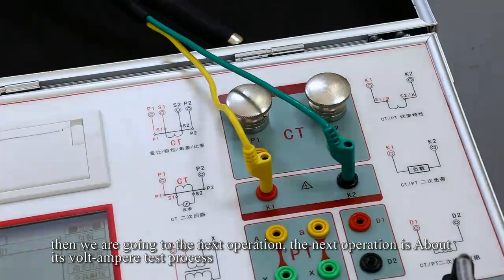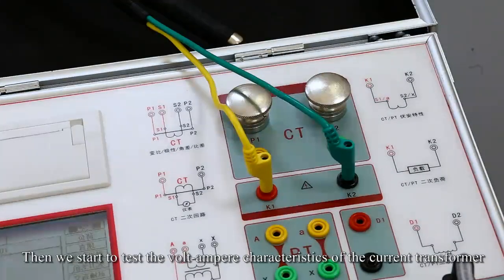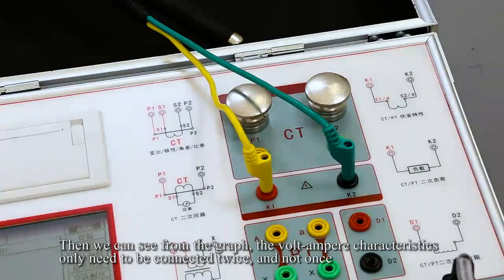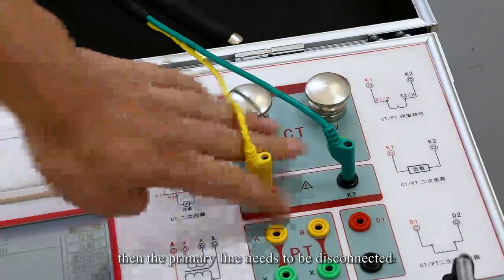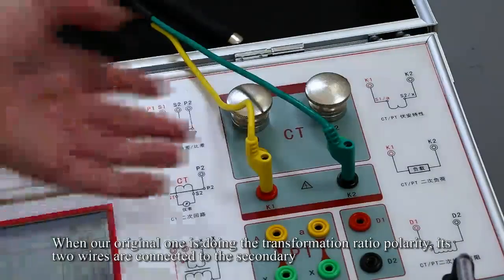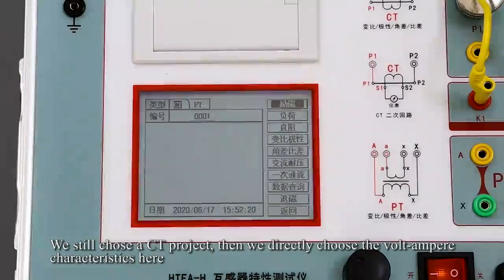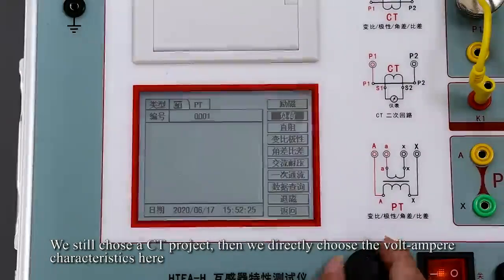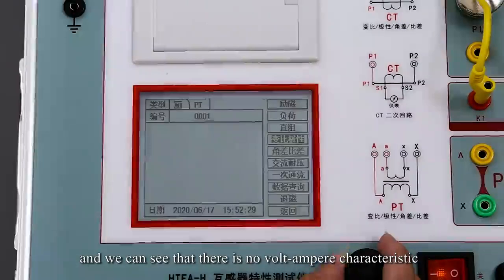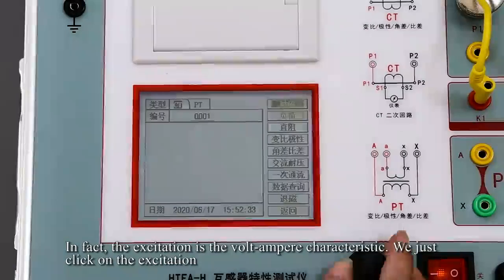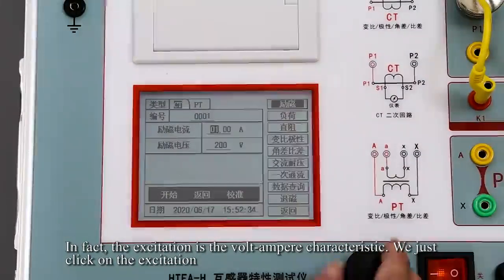The next operation is the volt-amp test process, where we test the volt-amp characteristics of the current transformer. From the graph we can see that the volt-amp characteristic test only needs to be connected twice, and the primary line needs to be disconnected. When we did the ratio polarity test, the two wires were connected to the secondary, so we can conveniently move these two wires to K1 and K2 for the volt-amp characteristics. We still choose the CT project, then choose the volt-amp characteristics. In fact, the excitation is the volt-amp characteristic, so we just click on excitation.